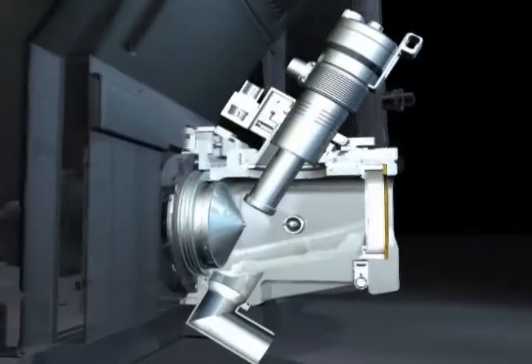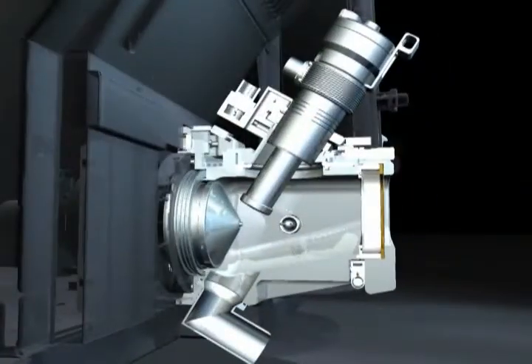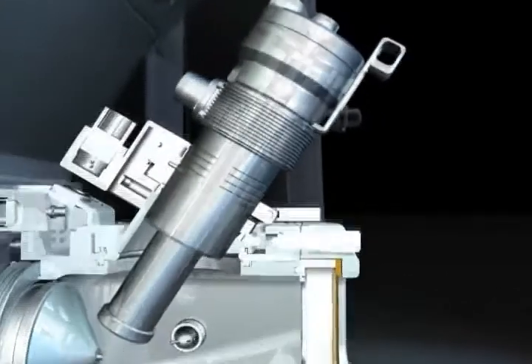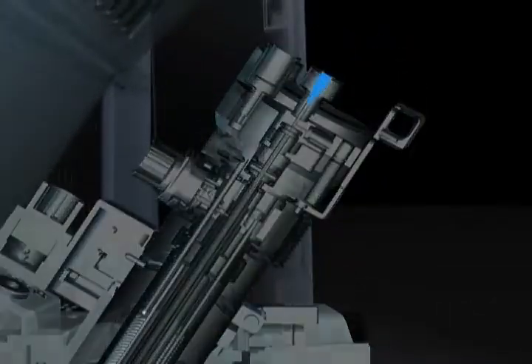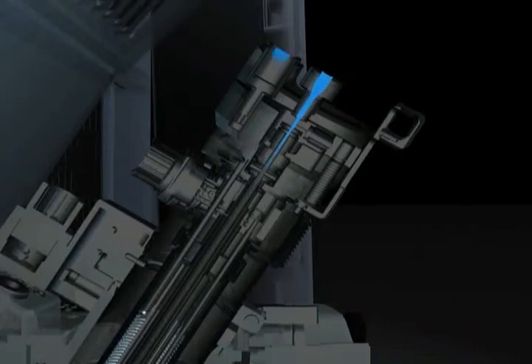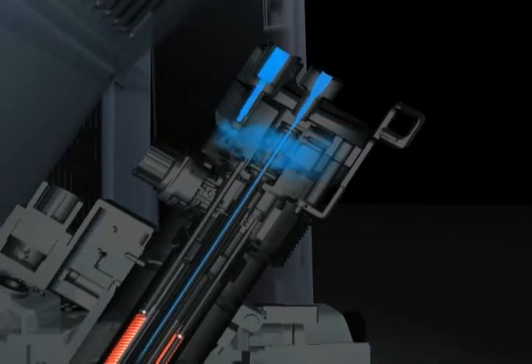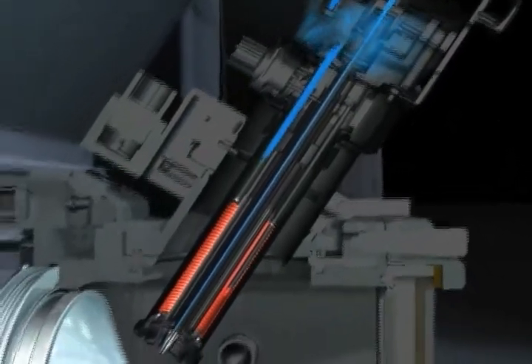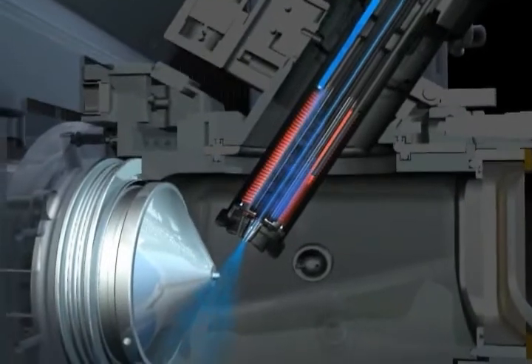What we did with the heated electrospray design was base it off our successful APCI probe technology. The heater on the APCI probe is well established, it's robust, so we wrapped a heat exchanger around this heater. Now the idea is to swirl the auxiliary stream of nitrogen gas around the heat exchanger. The swirling causes an increase in path length, which causes the gas to pick up heat.